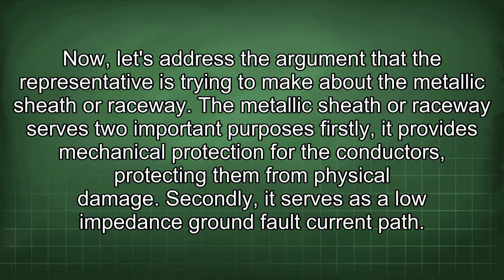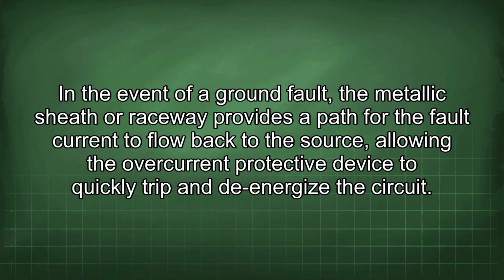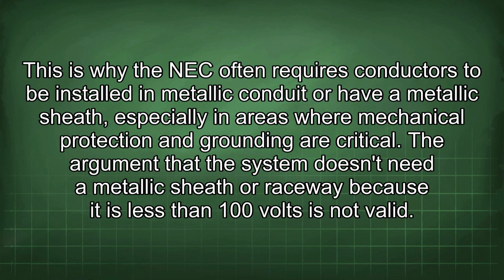Secondly, it serves as a low impedance ground fault current path. In the event of a ground fault, the metallic sheath or raceway provides a path for the fault current to flow back to the source, allowing the overcurrent protective device to quickly trip and de-energize the circuit. This is why the NEC often requires conductors to be installed in metallic conduit or have a metallic sheath, especially in areas where mechanical protection and grounding are critical.